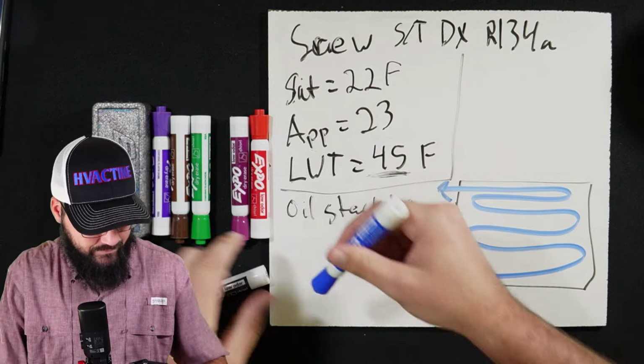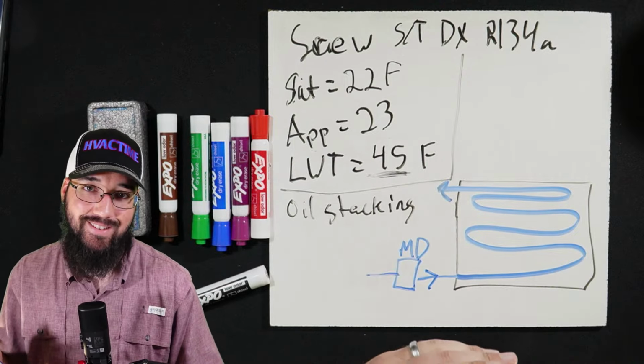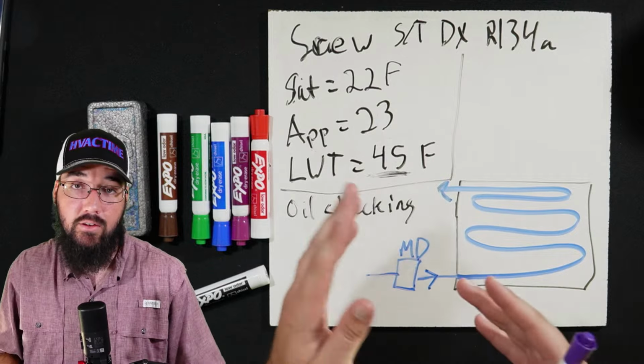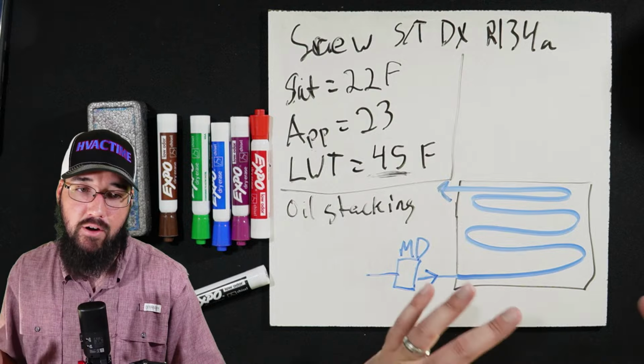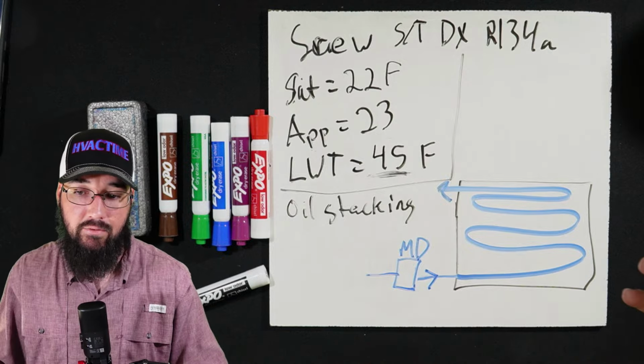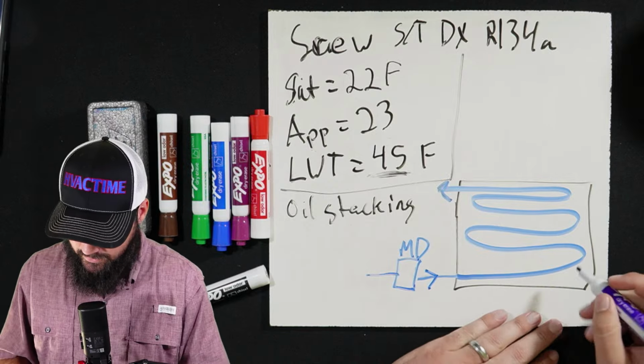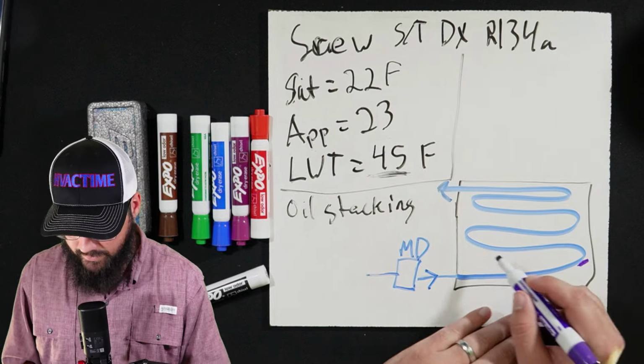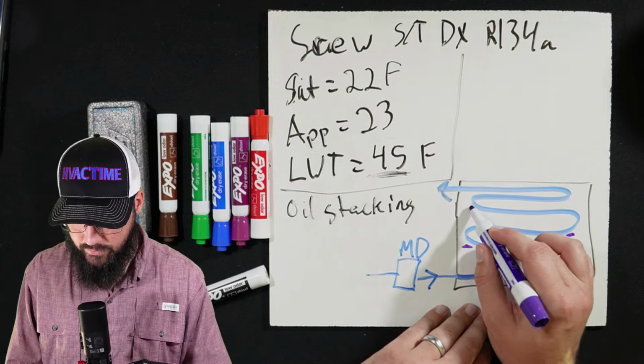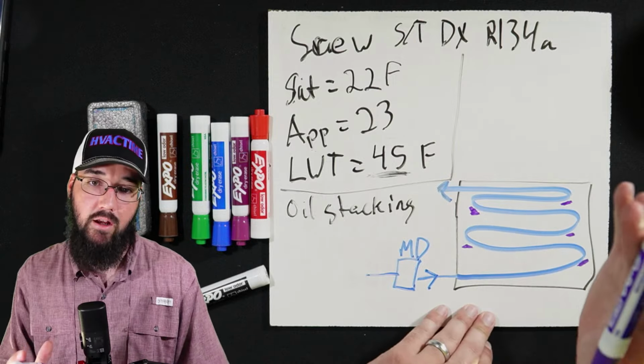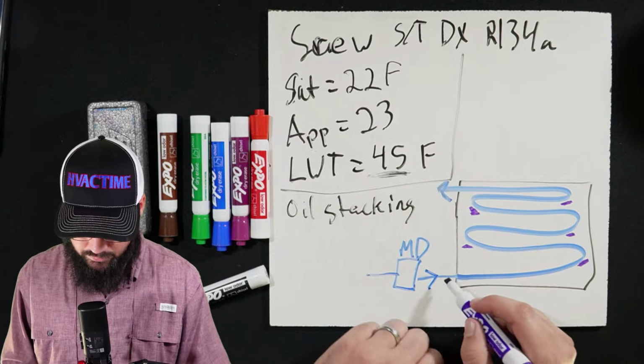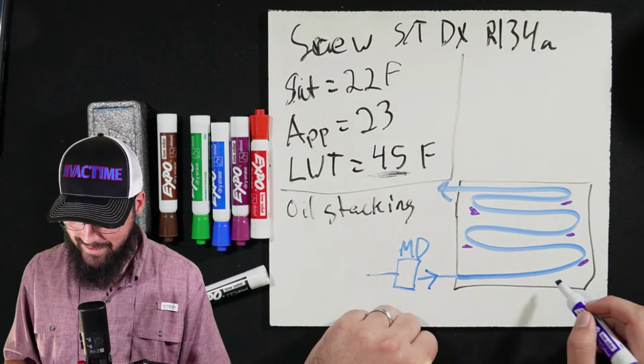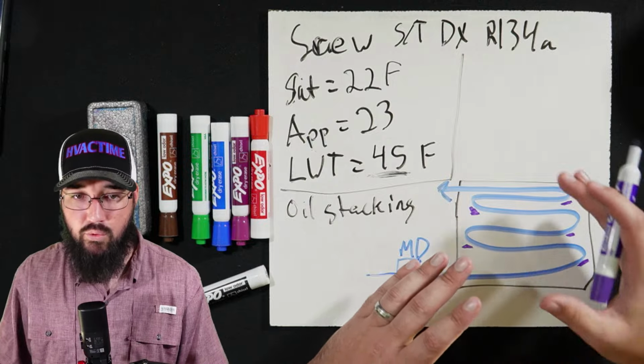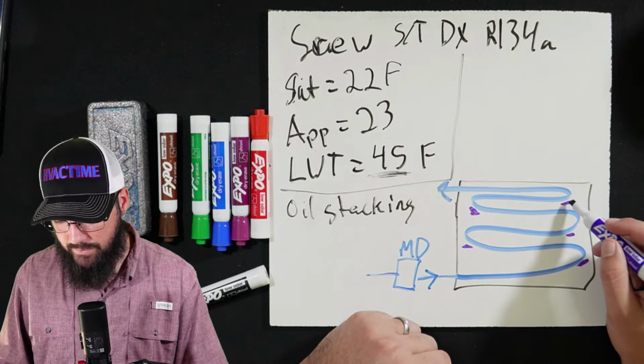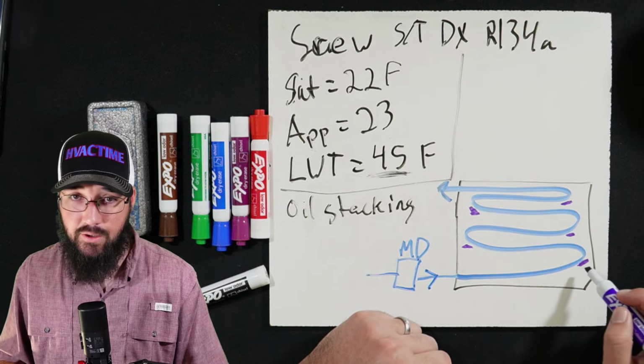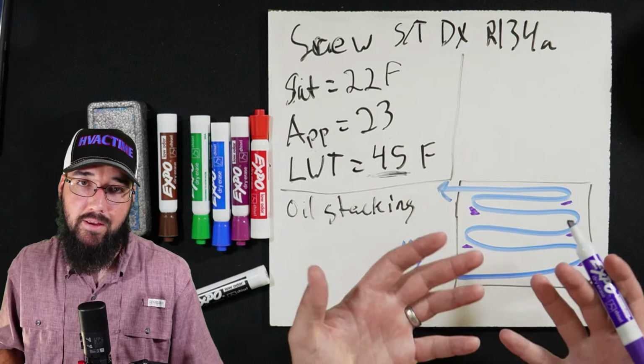What can happen when we run really low loads for an extended period of time? This could be as little as just a few hours worth of runtime at very minimal loads, and our compressor itself is just barely even staying on. Then what can happen is these elevation points right here, where we make turns and we have to work our way up, vertically up in the circuit, our refrigerant is moving so slowly that it's not able to get enough velocity on it to move that oil. And what happens is that oil slowly starts to accumulate at all these little low spots where we need to vertically make that oil rise.